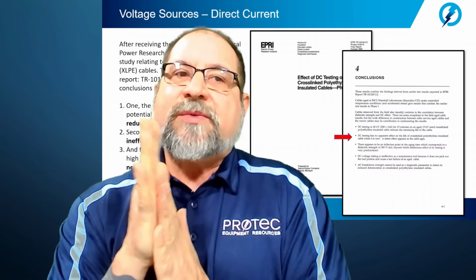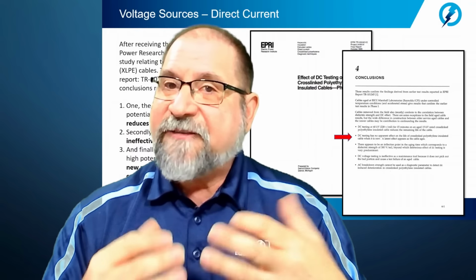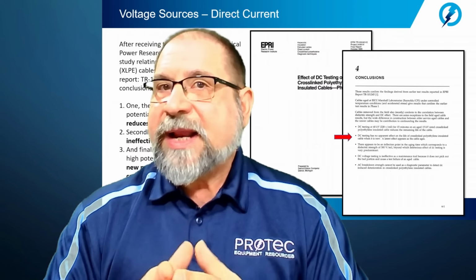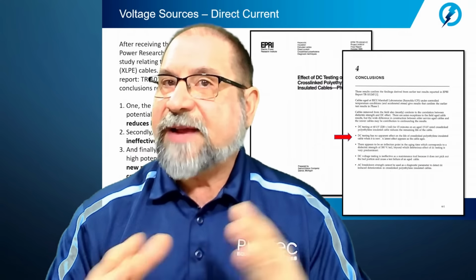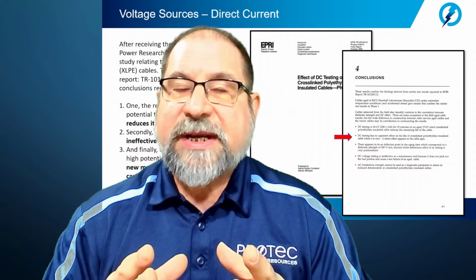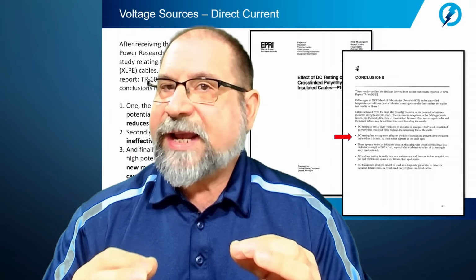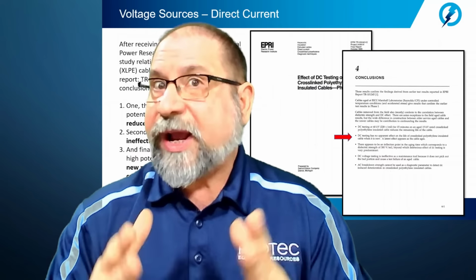Okay. Also, the report basically stated that DC is ineffective as a maintenance tool. Now, for those of you that may be familiar with DC testing and have done quite a bit of it, you may have noticed that when you are dealing with what I call a dry cavity type of fault, most times your DC insulation resistance test will show a beautiful high level of insulation resistance. And when you run your high potential test, you will find that the circuit, in most situations, will hold voltage, or you must go considerably above the operating level in order to get it to break down.